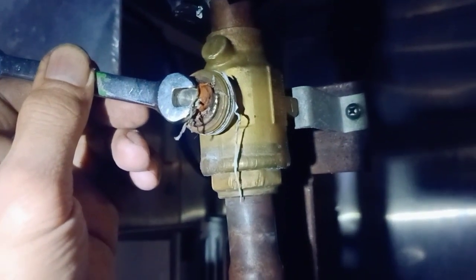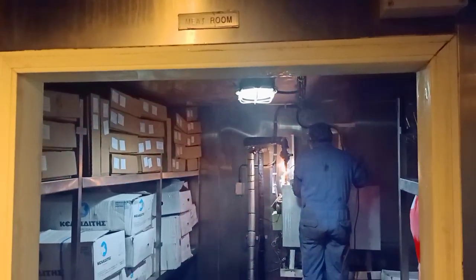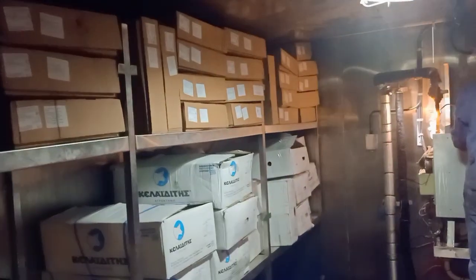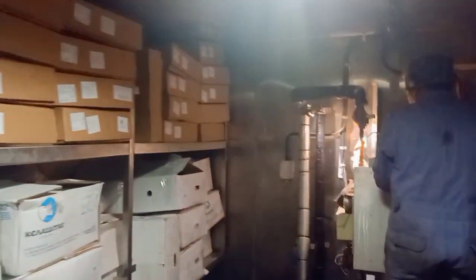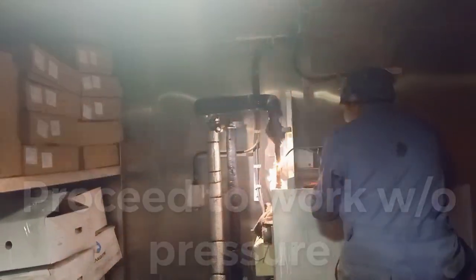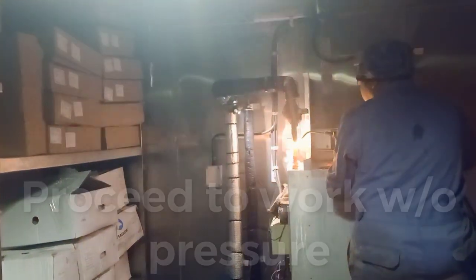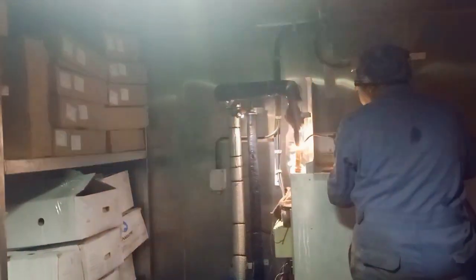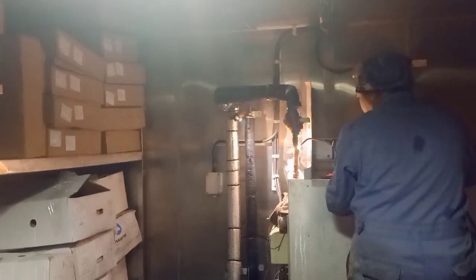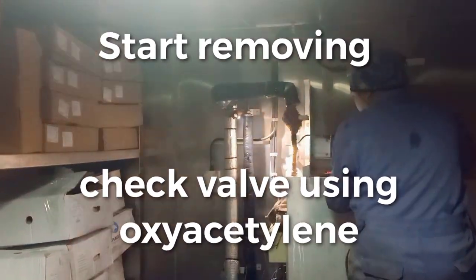Working without pressure from the system. We are now at the mid-chamber. We are now removing the non-return valve. All valves are already isolated. This is the suction-side valve going back to the compressor.